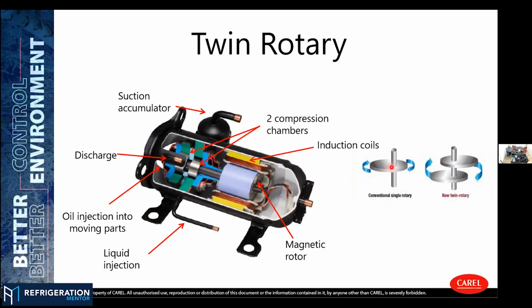A twin rotary compressor has a very interesting characteristic: when one side of the compressor chamber is doing the compression, the other one is relieving the refrigerant. So we kind of equalize forces, and we need a smaller motor to make this torque for the compressor. The big advantage of a twin rotary compressor is that we can have double the displacement, and we do not need double the motor. We can have a smaller motor. As you can see in the image, this twin rotary compressor can be installed horizontally like this one. So we can decrease the size of the unit, and we can install it practically everywhere, because you can operate the compressor in a horizontal orientation or in a vertical orientation like this one.